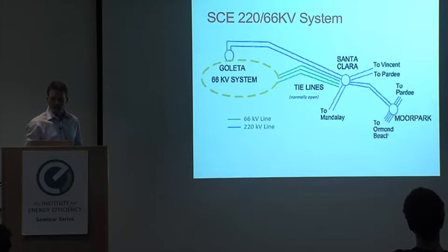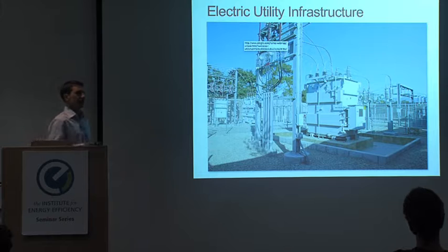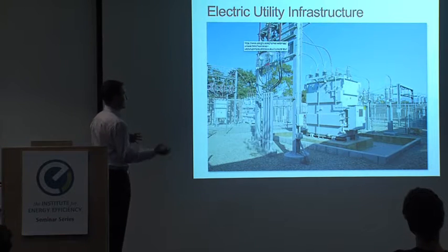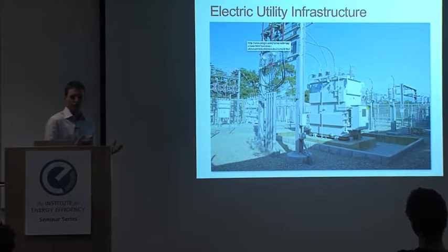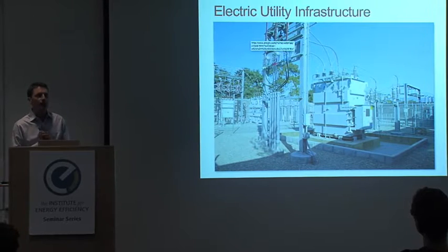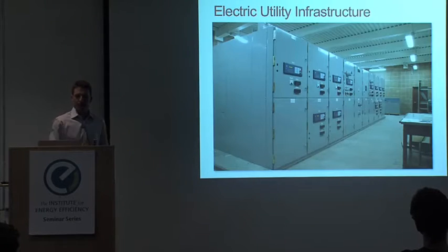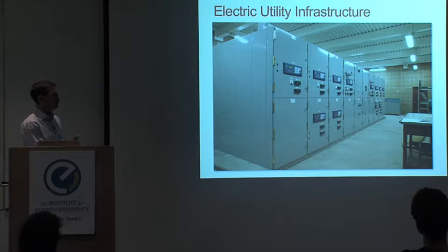So we've got our own substation on campus, and what we do there is take 66,000 volts from the utility. We've got a 66 to 12 kV transformer system, actually 2 of them in parallel, and that's how we serve the campus. This is our campus switchgear — 12,000 volts. There's a lot of smarts in this system.